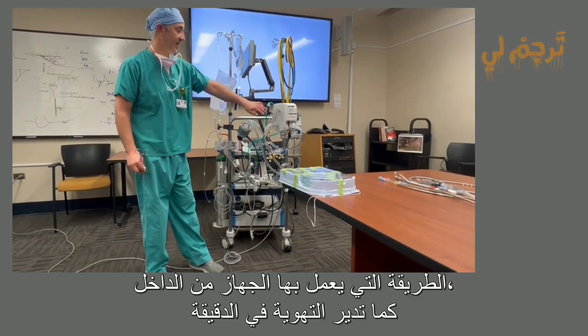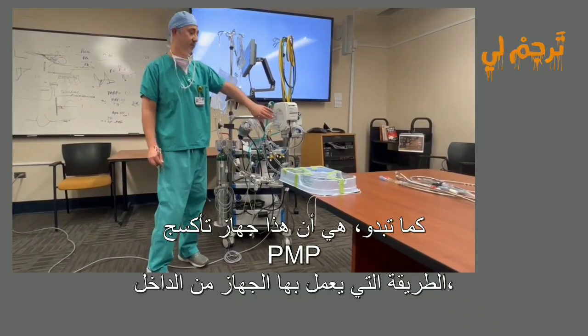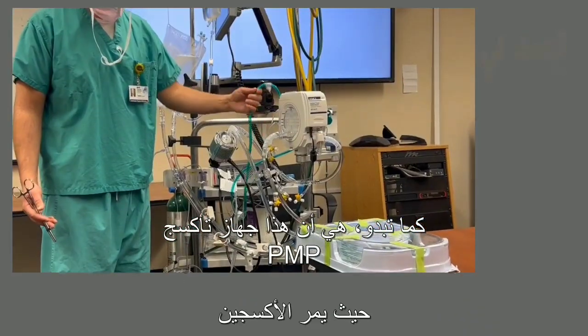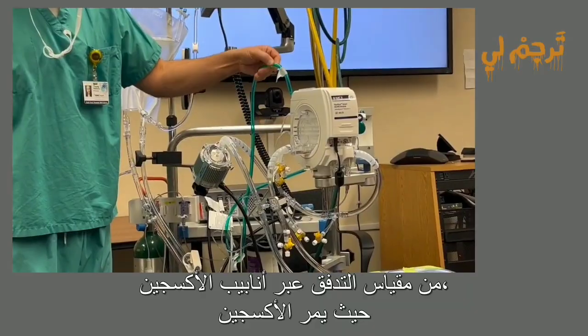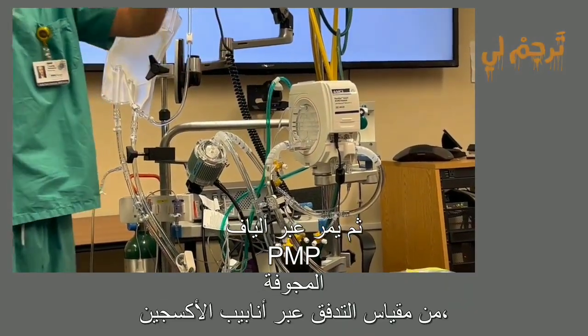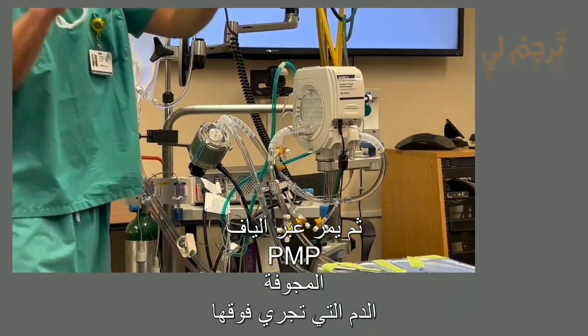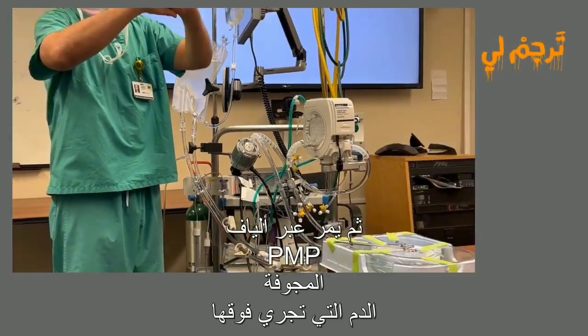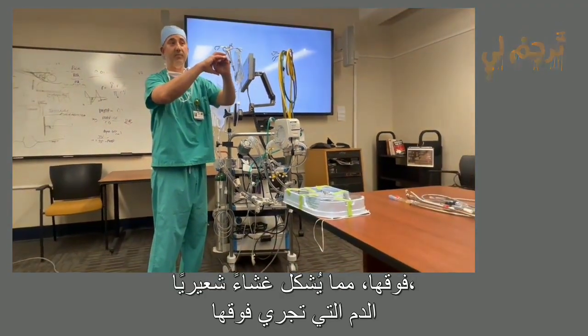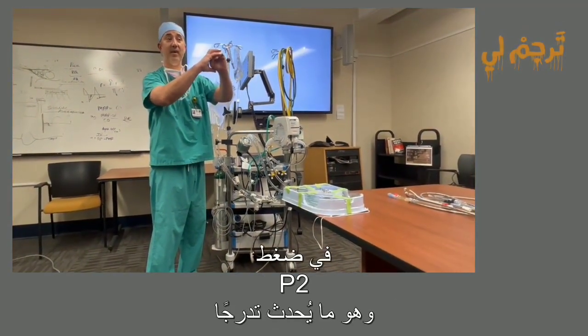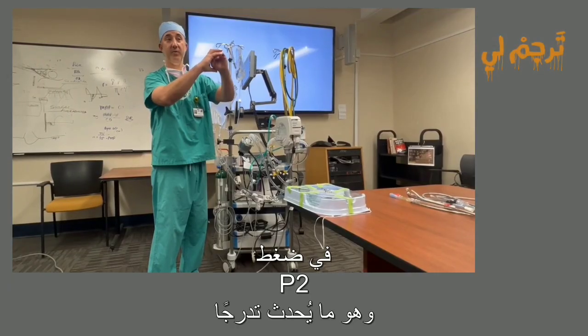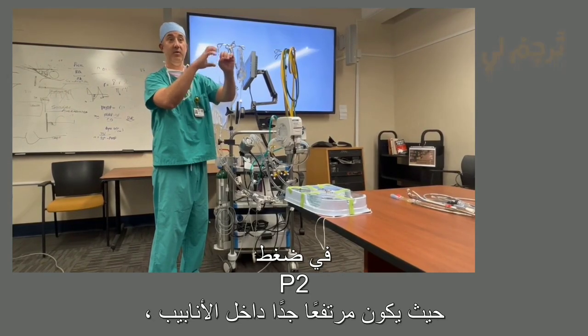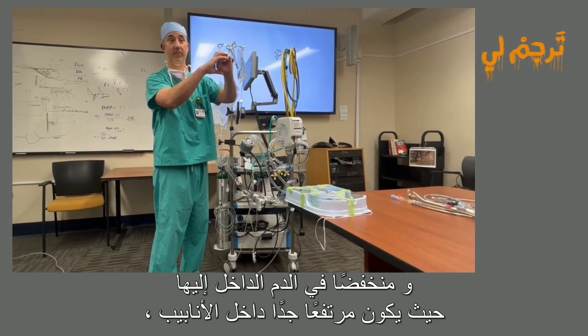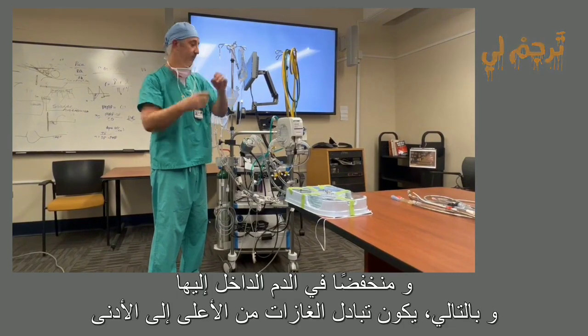The way it really works inside here, the way it looks like, is this is a PMP oxygenator. And so the oxygen from the flow meters comes through the oxygen tubing and goes through these PMP hollow fibers. Blood runs over it, and that basically creates like the alveolar capillary membrane. And that's where you have that pressure gradient of the PO2 being super high inside the tubes and low in the blood that's going into it. And the gas exchange is high to low.